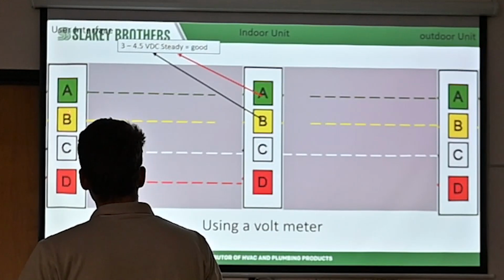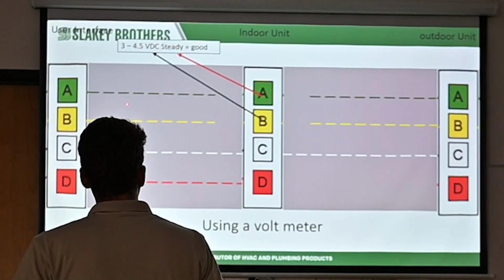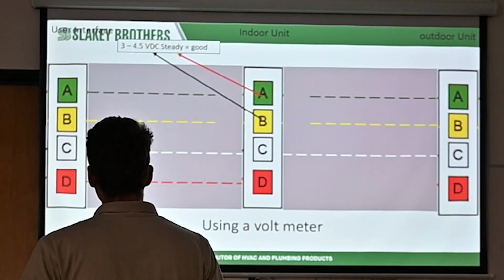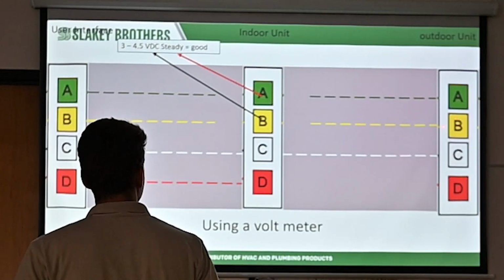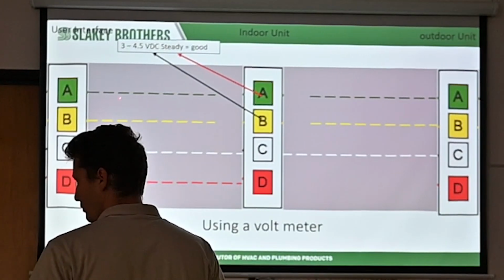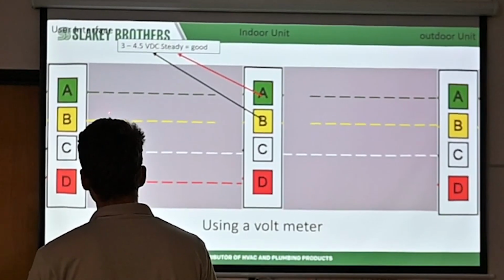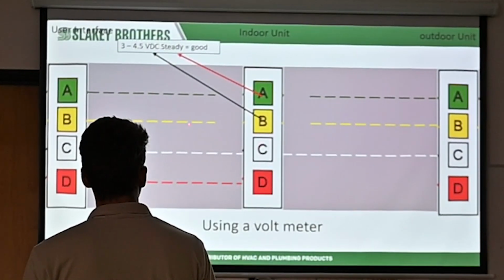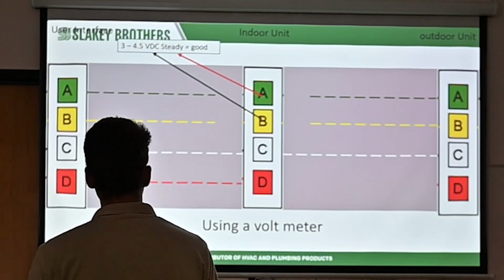That's going to be a problem with either the controller or the wire. When you lose communication to the outdoor, that's easy. You can just look at the outdoor system overall. But when you lose communication on the indoor unit, to everything, it means that between here and all of this, it's not seeing anything.